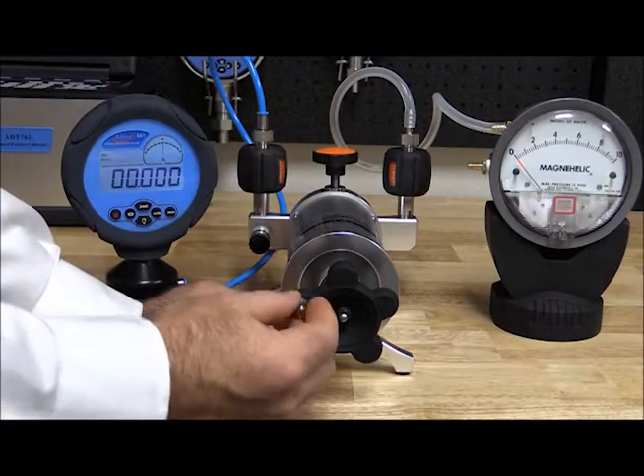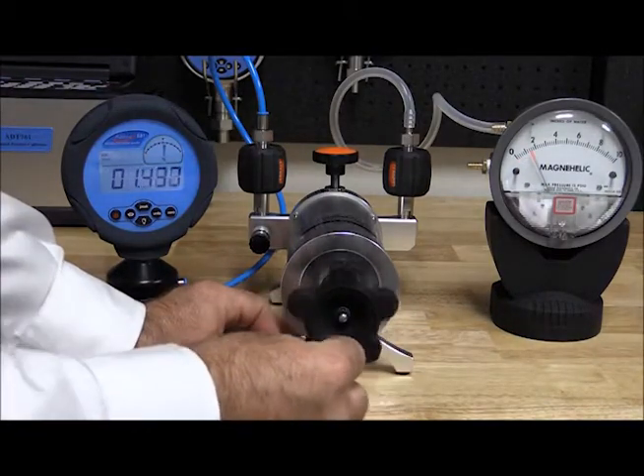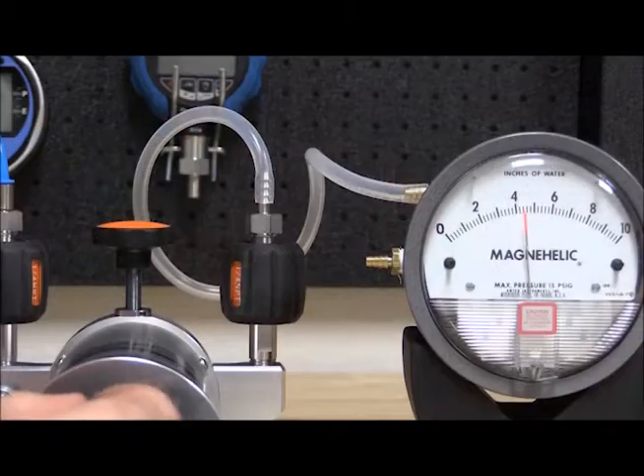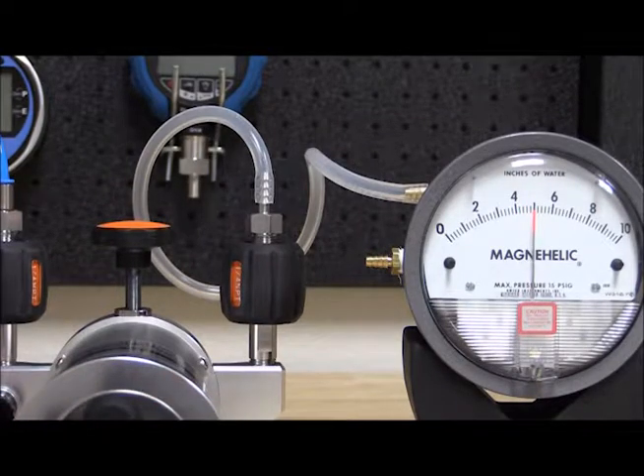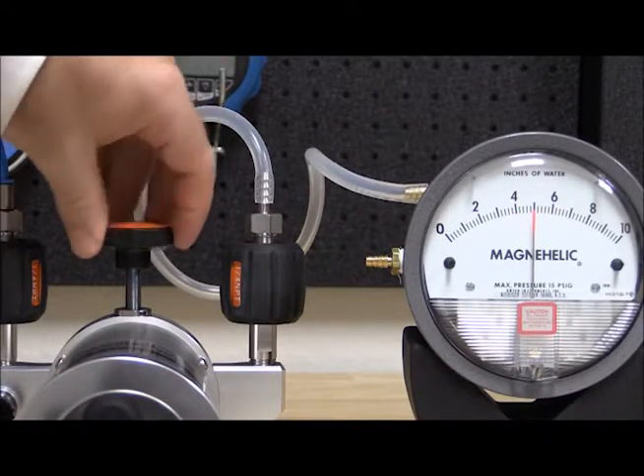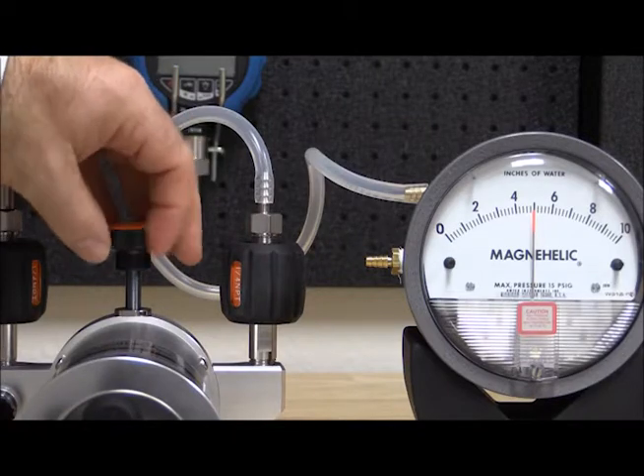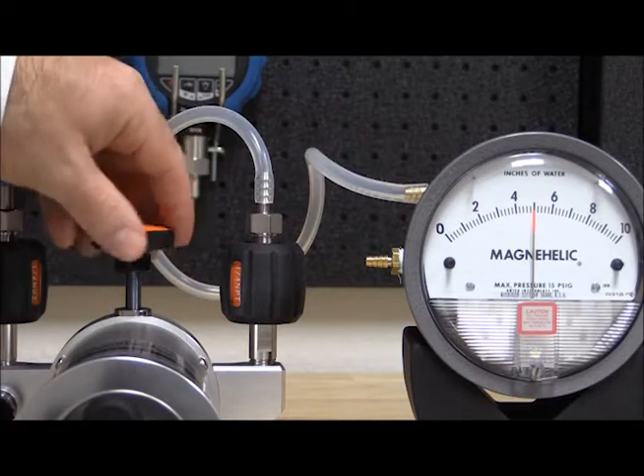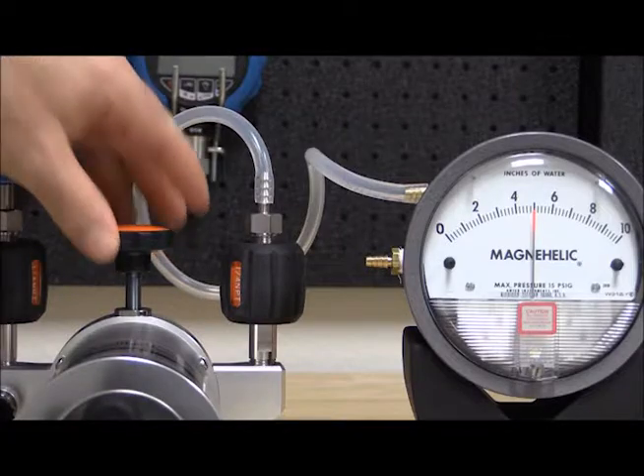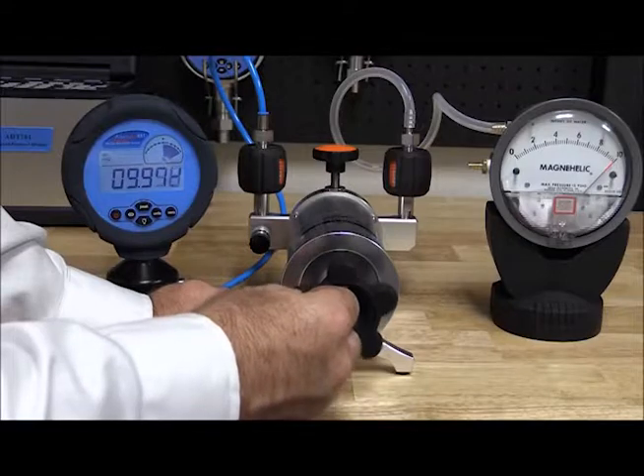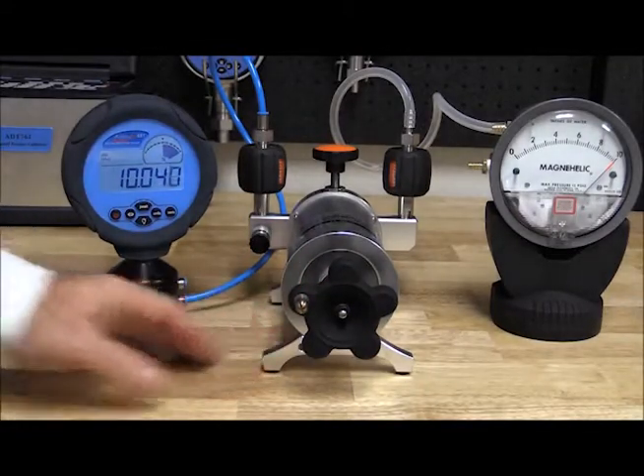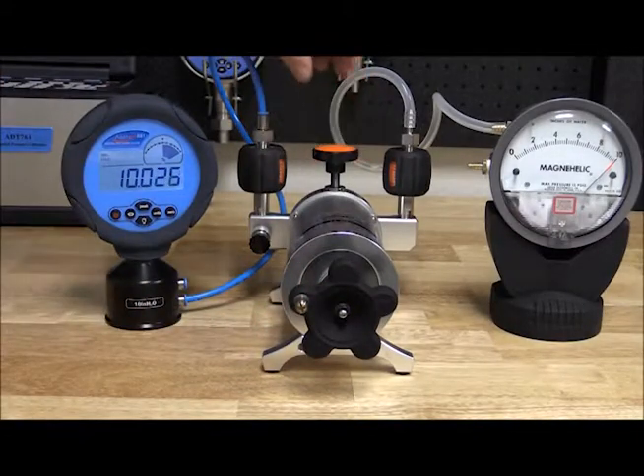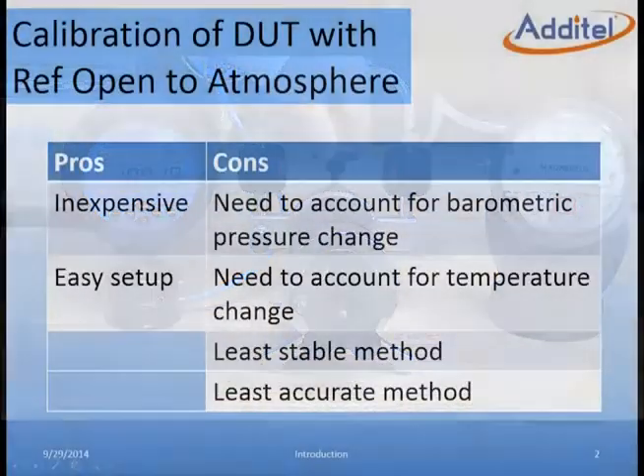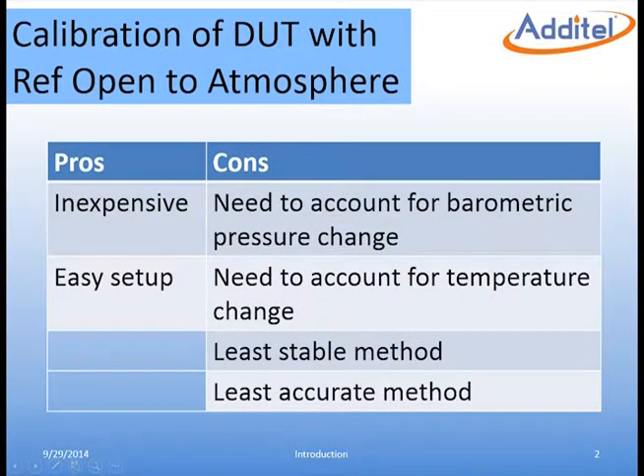Typically, 3 to 5 points are taken, both ascending and descending. By taking more than 2 points, we are able to check the gauge's linearity and hysteresis. To achieve cardinal points in the gauge, the high-quality screw press or fine adjustment knob may be used to dial in the exact pressure for the gauge. The Additel 901 pump uses an isothermal bellow chamber, which is designed to reduce the impact of environmental temperature changes. In this method, the setup is very simple and the equipment used is relatively inexpensive.